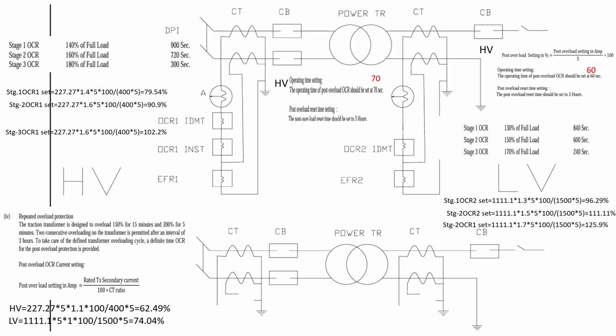So what we have done, you have taken the rated load current as 227.27, then 140% means 1.4, then it has been multiplied by 1 upon the CT ratio, 400 by 5, because the current will reduce in the CT secondary, and then percentage over the full load current of the relay, which is 5 ampere. So what is its percentage? It is multiplied by 100 and divided by 5, it is coming around 79.54%. Set this percentage in the OCR1. Then stage 2 is coming 90.9%, and stage 3 is coming 102.2%.